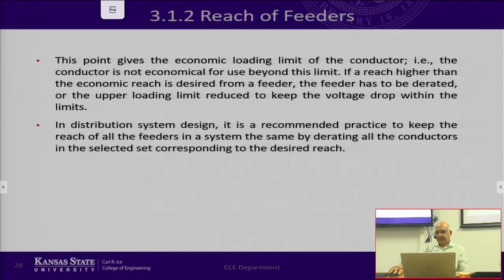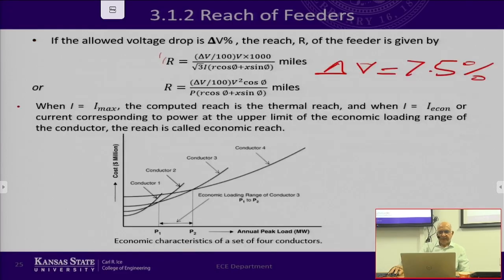One important thing to keep in mind is that the higher the P is, the lower the reach is going to be. The reason is that you are putting more power, which means more current, so the voltage drop is going to be higher, and your distance has to be reduced.